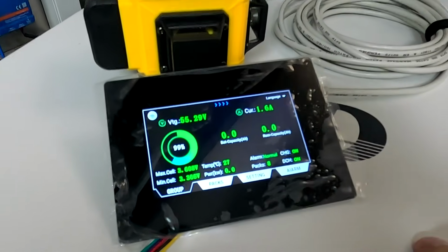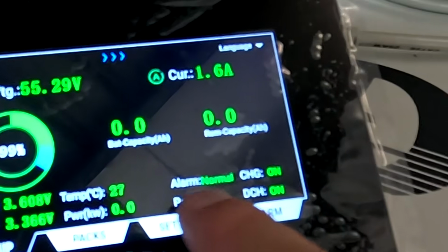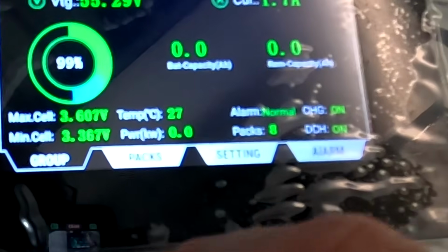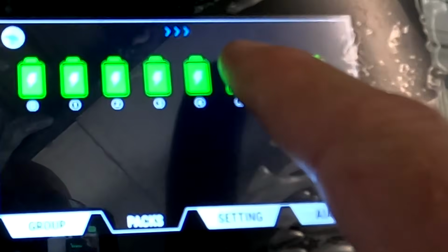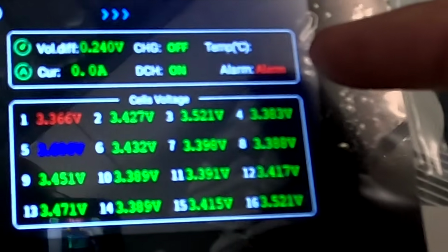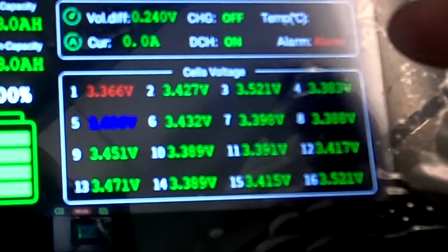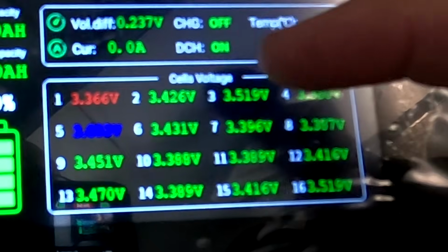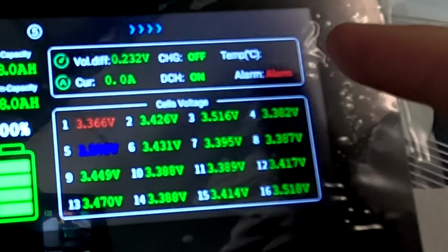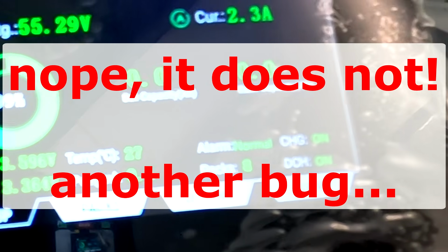But if we look at the master BMS, it says alarm normal - there's no alarm shown for any of the BMSs. If we go into packs, pack number 5 shows an alarm, but it doesn't say which one. You can see the charger is off, discharging is on, but this alarm doesn't come through to the master - it may not even reduce your charging current.